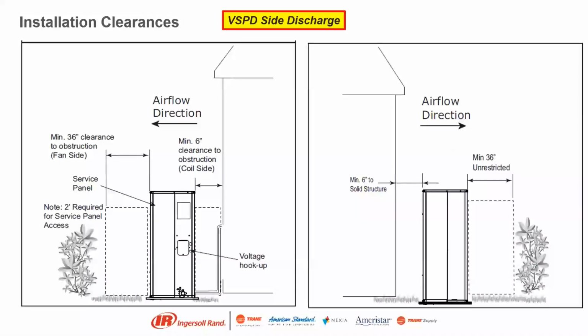Installation clearances are a minimum of 6 inches from the exterior. Two feet required from the front of the service panel for airflow. We have had halfway blockage, with railroad ties possibly getting stored in front of it. Be aware that output air will backdraft, and there's an outdoor air sensor right back here that can be relocated if need be. But keep that in mind. If there's something obstructing it, the air is going to push back and affect that ambient sensor.